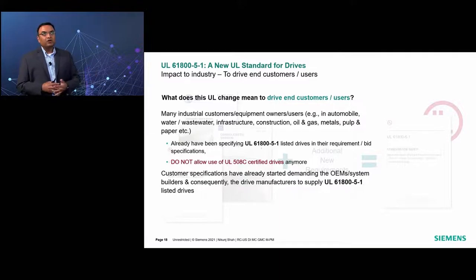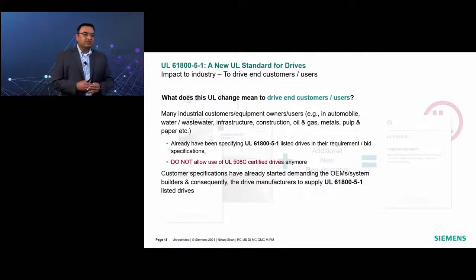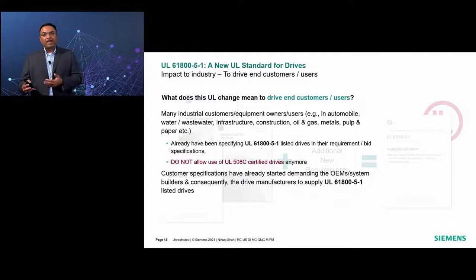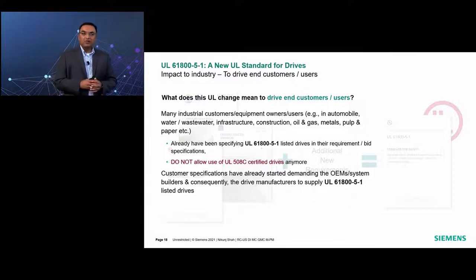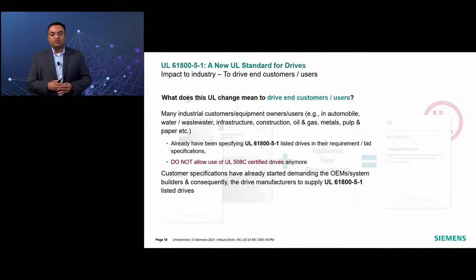Especially after the withdrawal of 508C last year, these customer specifications are demanding the OEMs and system builders or panel builders to supply the drive in their equipment, which is certified according to this new standard only. And therefore, they are putting pressure on the drive manufacturers to supply the UL 61800-5-1 listed drives only.